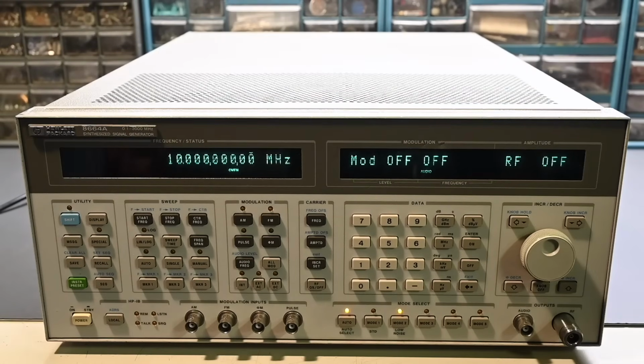So I'm going to let this sit for a little bit until the oven indicator light goes off, and then we'll continue with doing some initial tests and checking. I haven't checked the output. I have no idea of the operating condition. The fact that it does pass the self-test is a very good indication. It looks like it's fully calibrated with no errors at this point. So that's a good indication, again, that the signal generator is probably working reasonably well, but we need to take a look at the output. I'll put that on the spectrum analyzer and also connect it to the frequency counter. Let's get an idea of the operating condition, see if there's any issues going on.